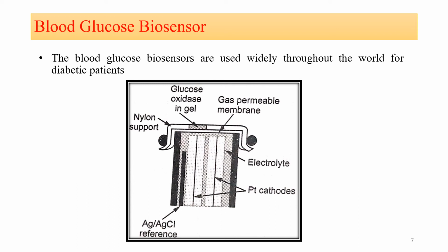Now three means are available for measuring the glucose concentration with electrochemical transducers. First, the fall in oxygen, that is O2, as the reaction proceeds. Second, the production of H2O2, and third, the change in pH with the production of D-gluconic acid. A typical sensor that uses an electrochemical transducer measures the glucose concentration based on the change in O2 in the glucose oxidase catalyzed reaction.